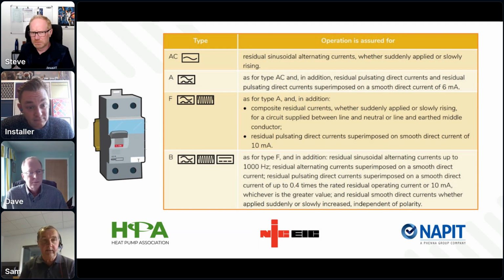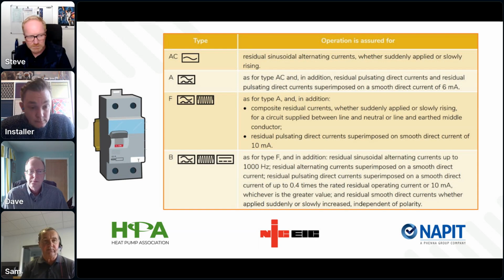Yeah, absolutely. You know, go back to the product manufacturer and get them to confirm that it does comply with all the product requirements of a type B. And as Steve said, it's got enhanced features, which then allows it to offer others. But so long as the manufacturer confirms that yes, it complies with type B, then that's the information that you need to use to say that yes, it's a product that's specified in 7671 currently.